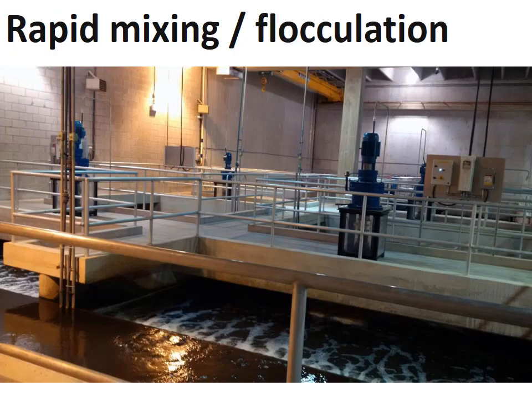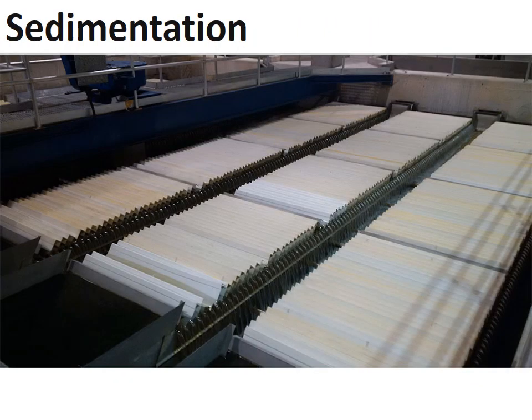The first step is rapid mixing, where a polymer is added to the water. The polymer attracts any dirt in the water and forms large clumps called flocs. From there, the water and the flocs move to the second step called sedimentation, where the flocs separate from the water and settle to the bottom of the tank.